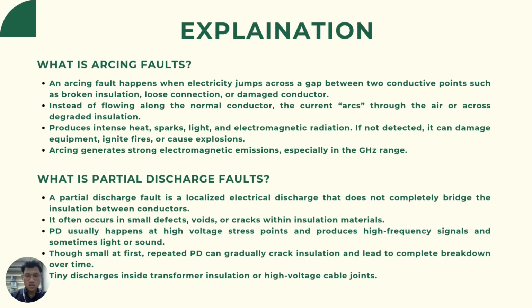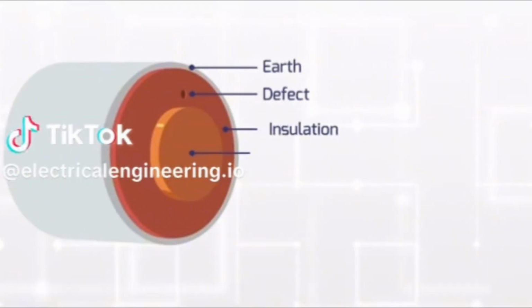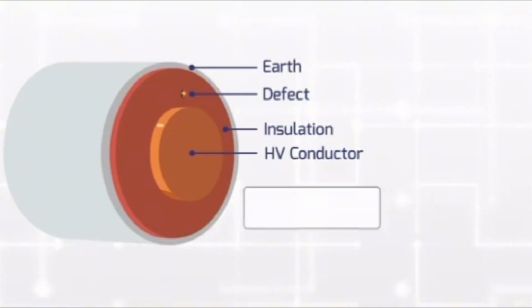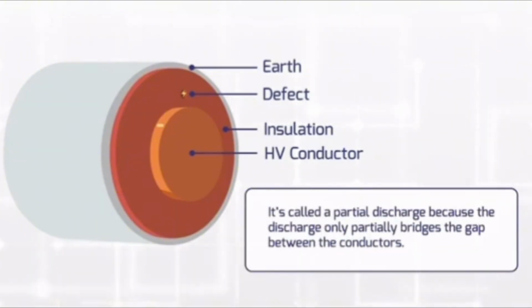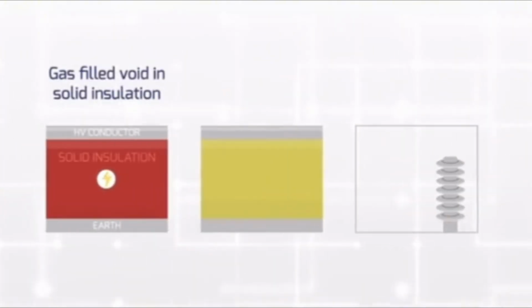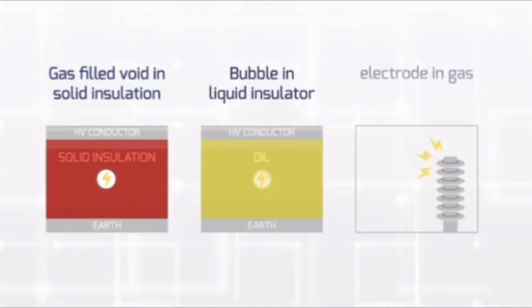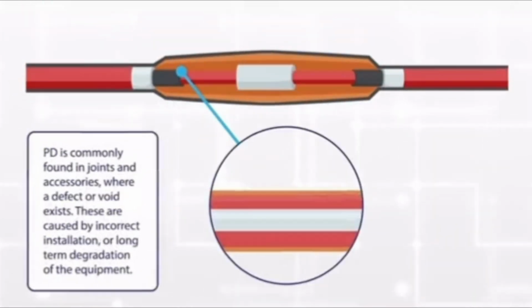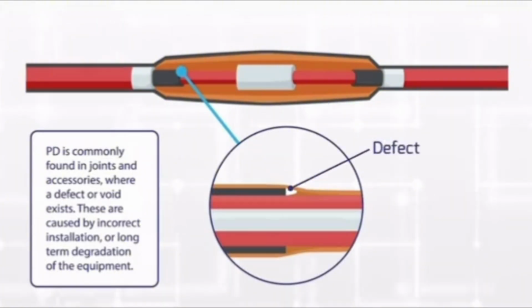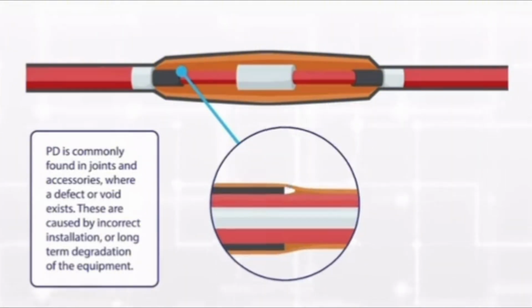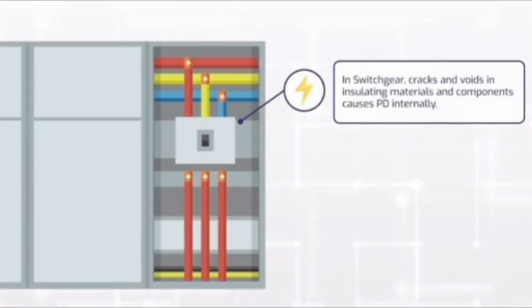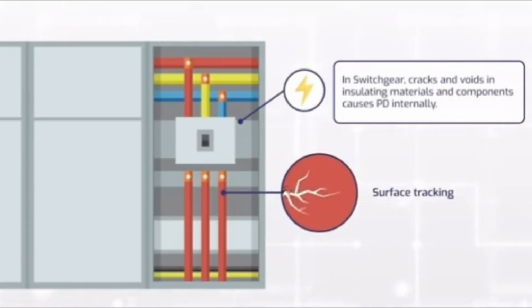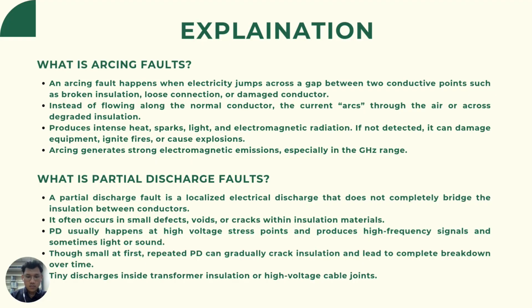Secondly, what is the partial discharge fault? A partial discharge fault, or PD, is a localized electrical discharge that does not completely bridge the insulation between conductors. It often occurs in small defects, voids, or cracks within insulation material. PD usually happens at high voltage stress points and produces high frequency signals and sometimes light or sound. Though small at first, repeated PD can gradually crack insulation and lead to complete breakdown over time. An example is tiny discharge inside transformer insulation or high voltage cable joints.